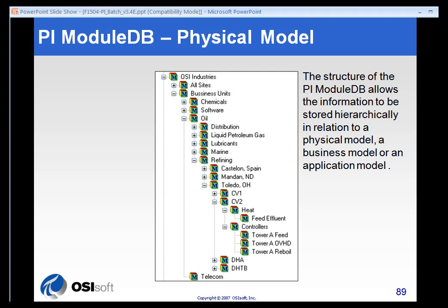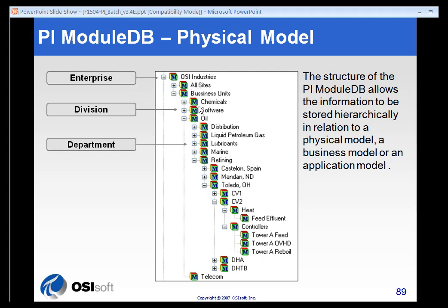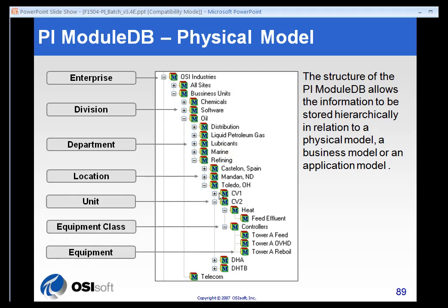When people build out their module databases, many elect to use the physical model. Here is an example: OSI Industries, a fictional entity. We start at the enterprise level and drill down to division, department, and location — a physical representation of the company. We drill down through business units and different departments, then finally locations, until we get to units and equipment. By the time we reach units and equipment, we're usually at something physical that has aliases, which are process variables, or has properties — and properties usually describe something about the physical unit.